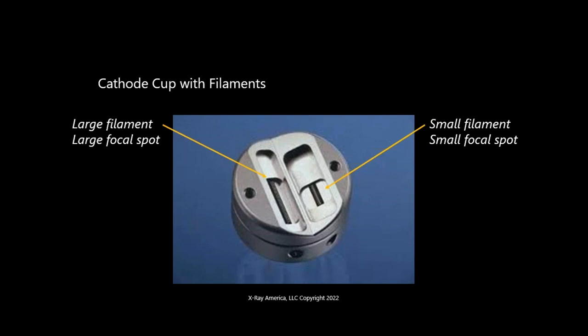Yeah. Well, these diagnostic tubes, it's amazing that they work. But when you get into CT, the most amazing thing is the amount of Gs you get. So now the holy grail in CT is 0.2 second rotation. What that means is that this tube, which is more or less the size of a 33-gallon tank of oil for weight and for mass, is spinning 5 times a second around the patient. When you get there, you're talking about 40 Gs.